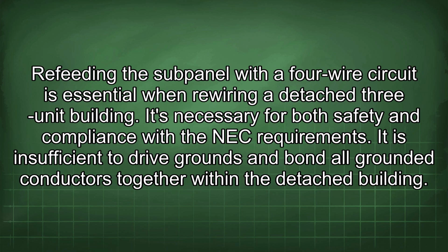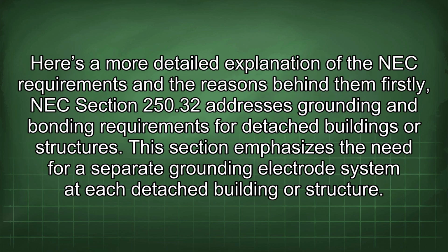Refeeding the subpanel with a 4-wire circuit is essential when rewiring a detached 3-unit building. It's necessary for both safety and compliance with the NEC requirements. It is insufficient to drive grounds and bond all grounded conductors together within the detached building. Here is a more detailed explanation of the NEC requirements and the reasons behind them.